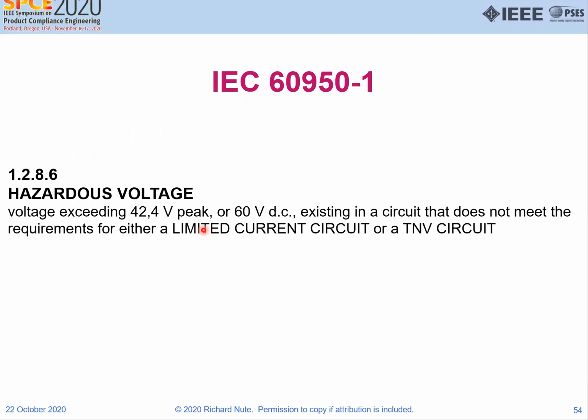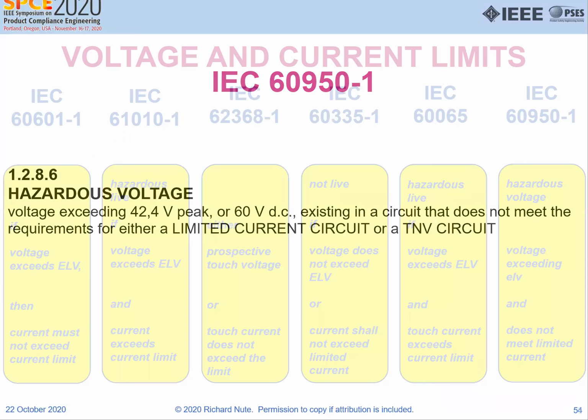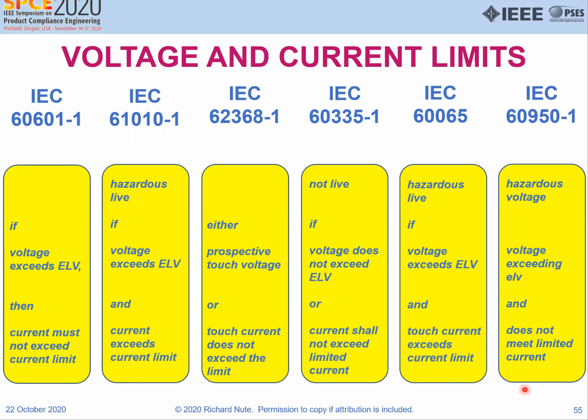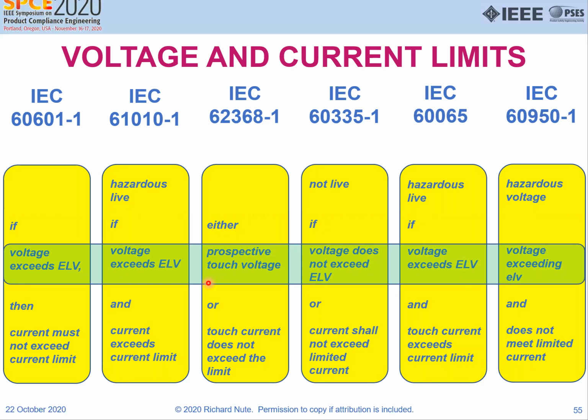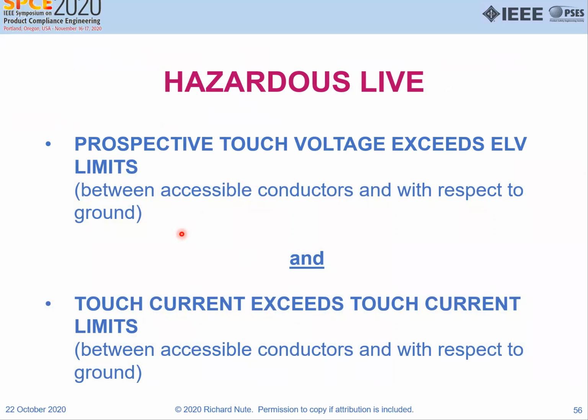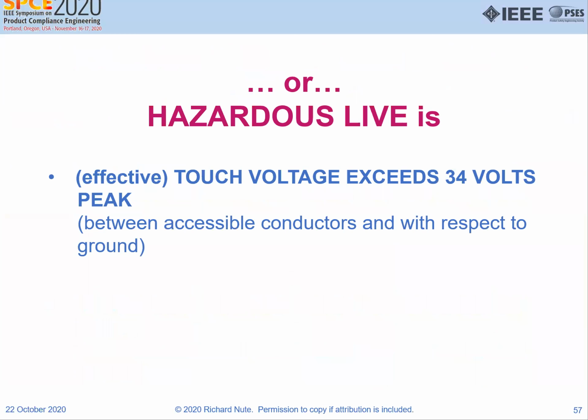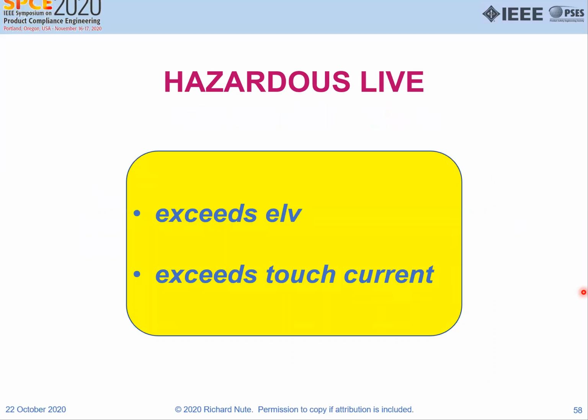Finally, we get to 950, which defines hazardous voltage as exceeding ELV and does not meet the requirements of a limited current circuit. So across here, we have voltages referenced to ELV, and we have current referenced to limited current. So hazardous live: prospective touch voltage exceeds ELV, and touch current exceeds touch current limits, whatever they have to be. And if we turn to the 1347 standard, touch voltage exceeds 34 volts peak. In any case, it's always the same: exceeds ELV and exceeds touch current. That's hazardous live.